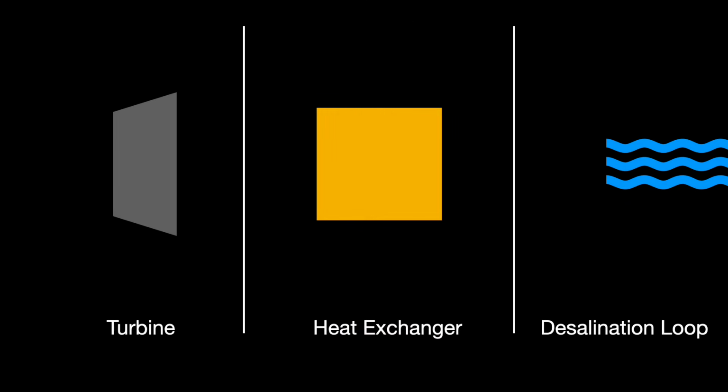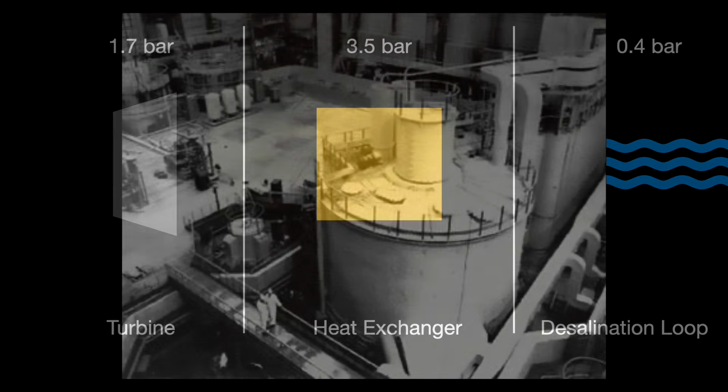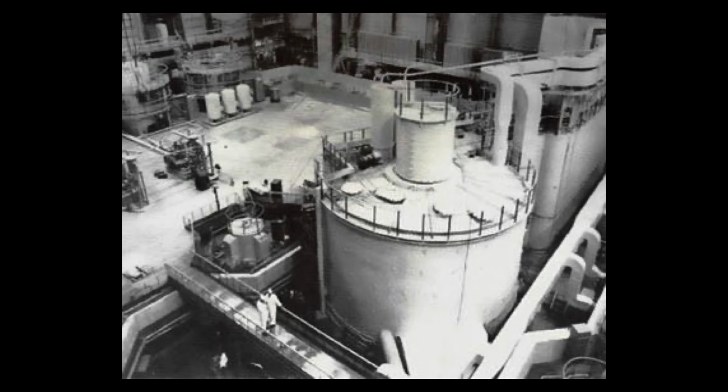To prevent this, engineers apply and monitor pressure differentials in the circuits. The various pressures keep leaks from spreading, and unusual discrepancies can be flagged as signs of leakage. This works. The experience so far in Japan, the United States, and Kazakhstan finds that nuclear desalination consistently generates water with tritium levels below international and country-mandated regulatory limits.